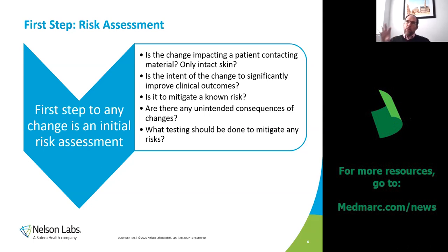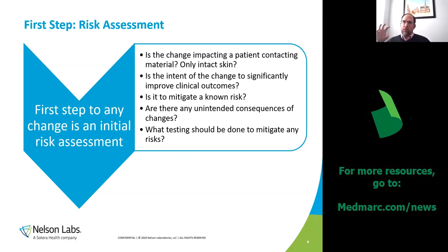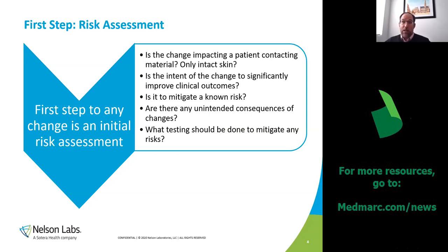If you have a surgical delivery device with a fluid path that runs saline or contrast solution through it, and you're changing a portion of the handle that has that fluid path, that's a patient-contacting portion — more concerning than if you're changing the handle that the surgeon holds onto while gloved. So that's your first step in the change assessment risk evaluation: does this change impact directly or indirectly to the body?